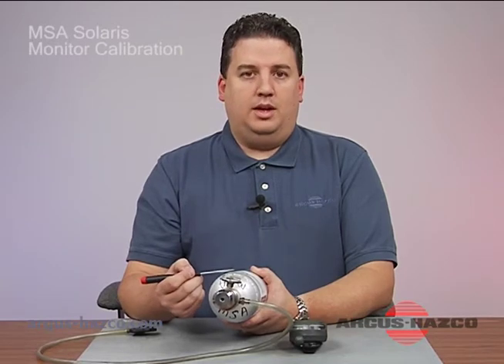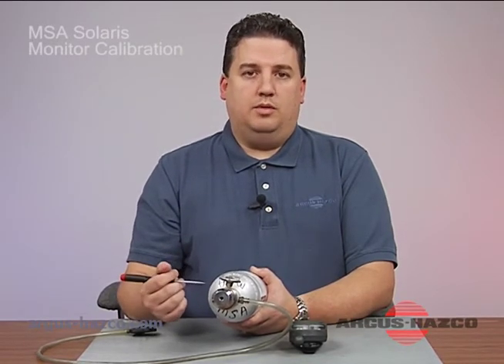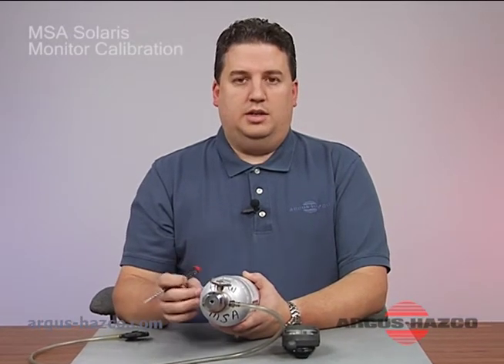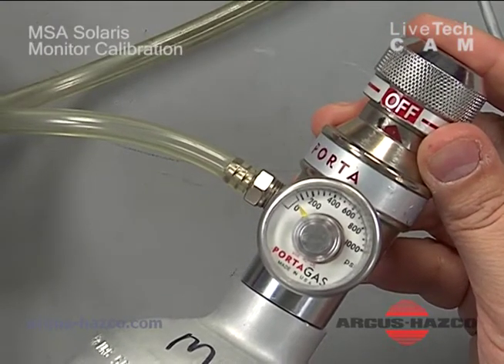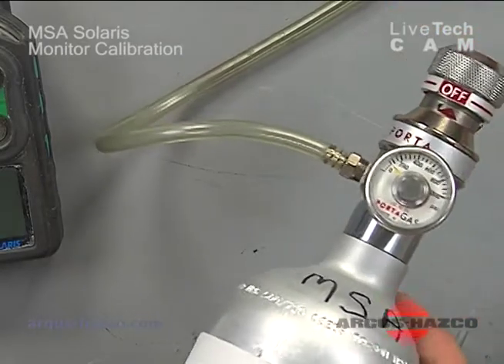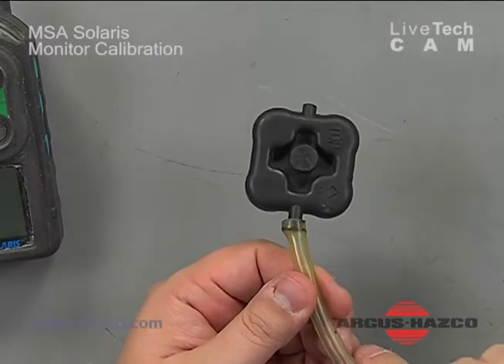By using methane, the instrument loses the ability to detect methane first. So as you expose it to methane, if you lose the ability to detect methane first, you know you have a problem with your sensor and can address it at that time. You also need a regulator to dispense about half a liter per minute, Tygon tubing to bring the gas to the instrument, and a cal adapter that you attach.